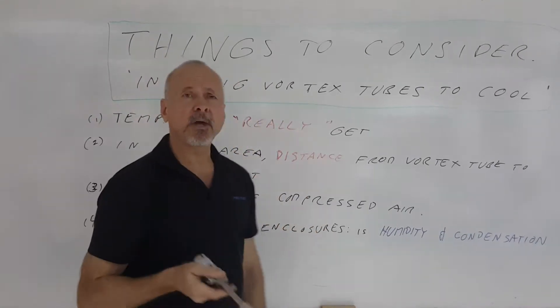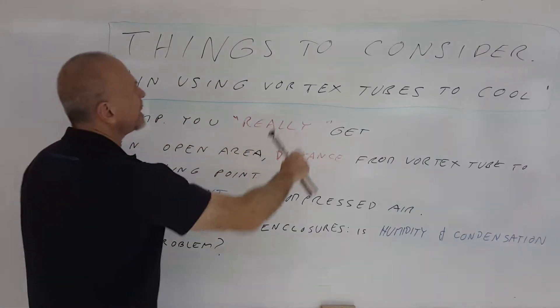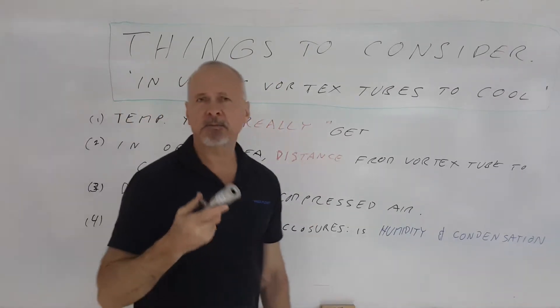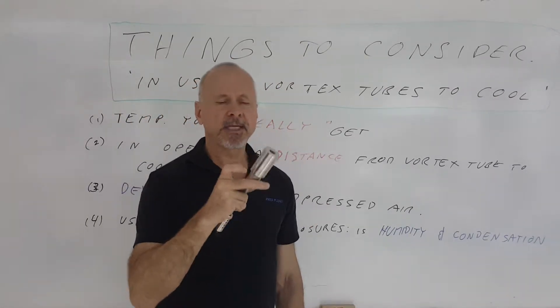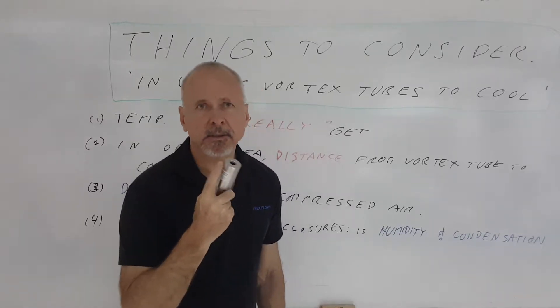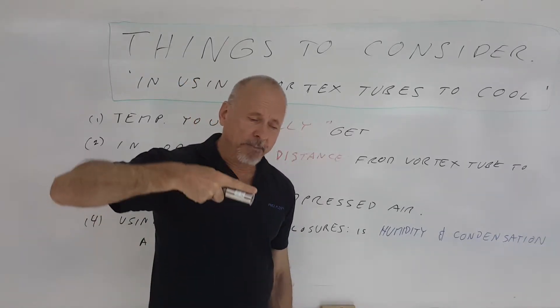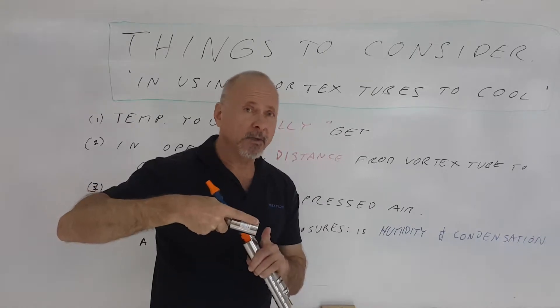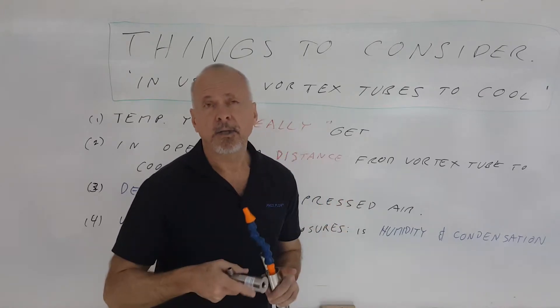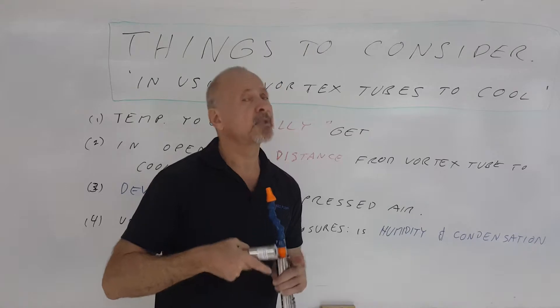So what are the things you have to really consider? First of all, what is the temperature that you really get that is usable? When you see vortex tubes promoted and specifications on them, they give you the temperature right at the inside of the vortex tube. So let's say you want minus 40 degrees Celsius or minus 40 degrees Fahrenheit on the inside of a vortex tube — the actual temperature you're going to get at the point of use is going to be higher, because as soon as that cold air comes out, it's combining with the surrounding atmosphere and will be affected by it.